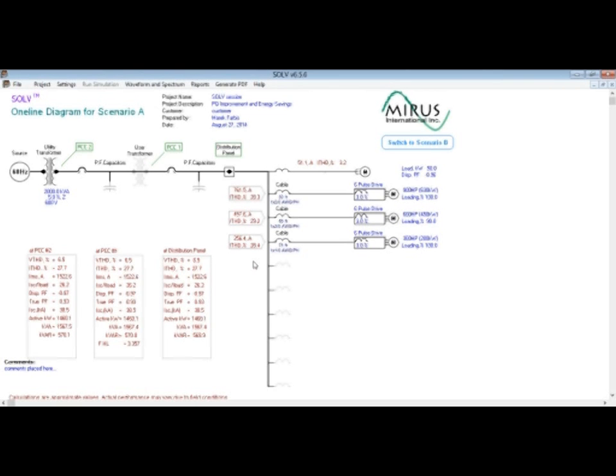And we can see that even with the lower impedance utility supply, the voltage distortion increases substantially when the transformer size is decreased to 2000 kVA. Voltage distortion in this case reaches 6.5%, which is a little bit higher than the commonly accepted 5% limit.